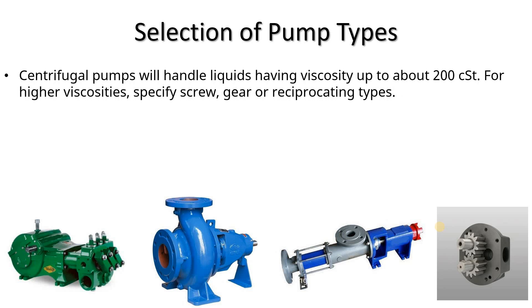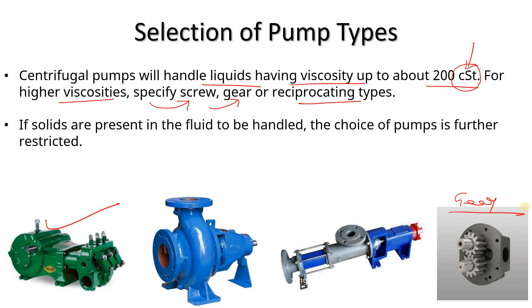If I talk about viscosity — centrifugal pumps can handle liquid viscosity up to 200 CST (centistokes). Can you let me know in the comments which physical quantity has this unit? If your liquid has a viscosity up to 200 CST, you can use a centrifugal pump. But for higher viscosity, you cannot use a centrifugal pump — for higher viscosity we go towards screw pump, gear pump, or reciprocating pump. You can also observe this in your industry.